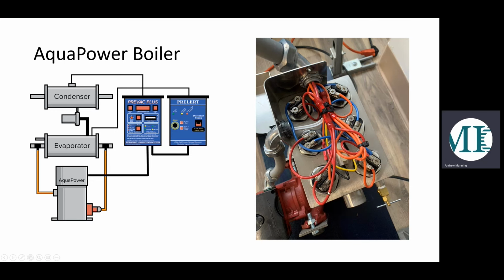Finally, this is just the inside of the boiler here. So we have 6 heating elements. We do recommend these get changed every 10 years as just a maintenance point. But other than that, everything else is built to last a very long time. This is where the temperature switch and thermistors are as well.